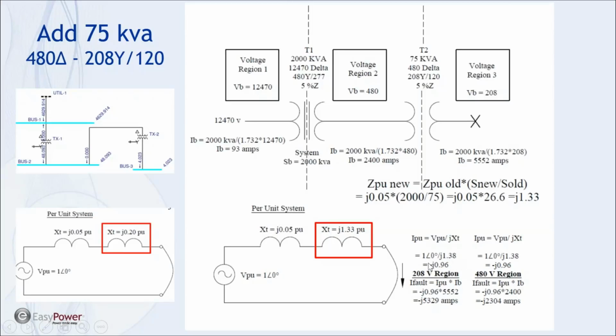That gives us the per unit fault current of 0.96, which may sound a little bit funny, but you've got to remember we're down here in the 208 volt region on the low voltage side of a 75 kVA transformer. But our fault current is going to be higher than 200 amps. By the way, the rated current on this transformer I think turns out to be 208 amps. Okay, but when we multiply that 0.96 by the base current that is established from the base VA of 5552, we get a fault current of 5,329 amps. And so that's on the 208 system.